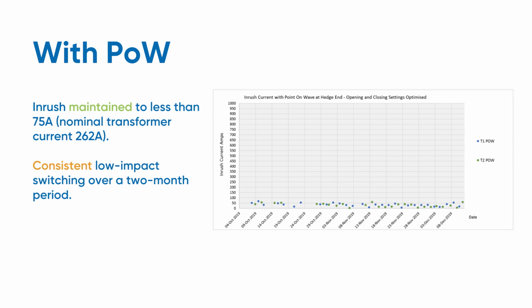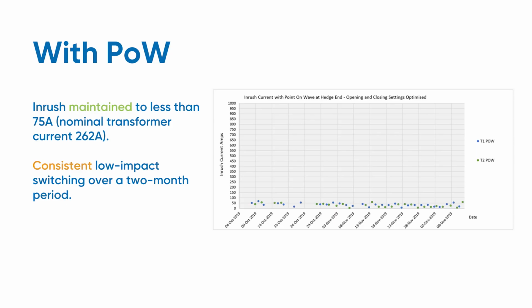So this would not have caused any impacts in terms of P28 harmonics on the customer's supply. And they saved lots of money in terms of the no-load losses. They estimated if they put this out over their network, it would result in millions of pounds of cost savings in terms of no-load losses, so a significant amount.